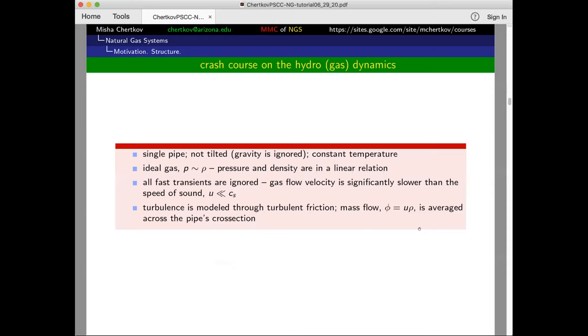Modeling-wise, you need to make some assumptions, and you can back those up and make them more general. For a single pipe, you assume it's not tilted — not going into mountains. You can account for gravity. Temperature is constant, which is not necessarily always the case. It's ideal gas, which is pretty accurate — pressure and density are proportional. That's also maybe a challenge if you inject hydrogen into your pipes, but I won't be discussing that much. All very fast front transients are ignored. Fast means faster than the speed of sound. Gas in pipes is under significant pressure, but the speed of sound is roughly what we have in air, and the actual physical flow of gas is much slower. That's a significant assumption and very rarely needs to be changed.